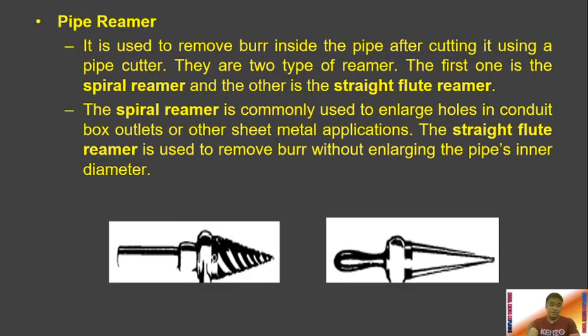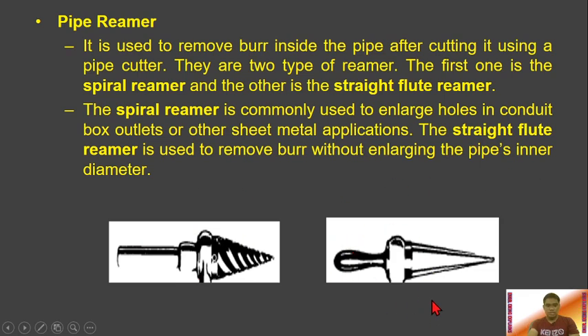Then we have the pipe reamer. After cutting a pipe with a pipe cutter, we use a reamer to remove the burr inside the pipe so that the wire insulation will not be stripped. There are two types: the spiral reamer, commonly used to enlarge holes in conduit boxes or in sheet metal applications, and the straight flute reamer, used to remove burrs without enlarging the pipe's inner diameter.